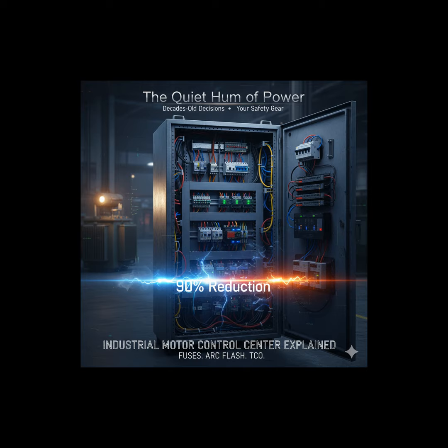I always find those older methods of protection fascinating. We're talking about components that are designed to fail, or at least trip in a controlled manner, based purely on thermodynamics. They are elegant, if a bit slow. Think about the traditional thermal mechanisms. You had the bimetallic strip, that's two different metals welded together. When they're heated by the motor current, they expand at different rates. And it bends. It bends, and that physically opens the control circuit contacts. Or you have the melting solder pot, where a calibrated alloy melts at a specific temperature, releasing a mechanism that trips the starter.